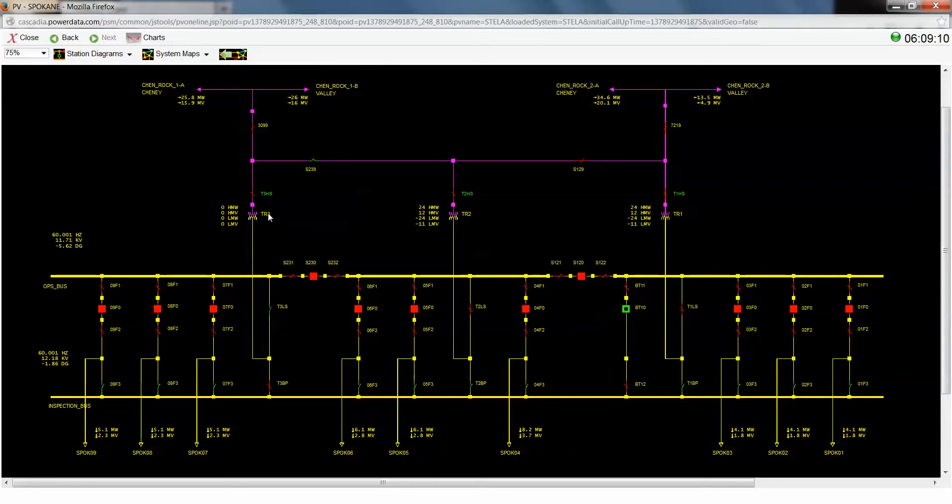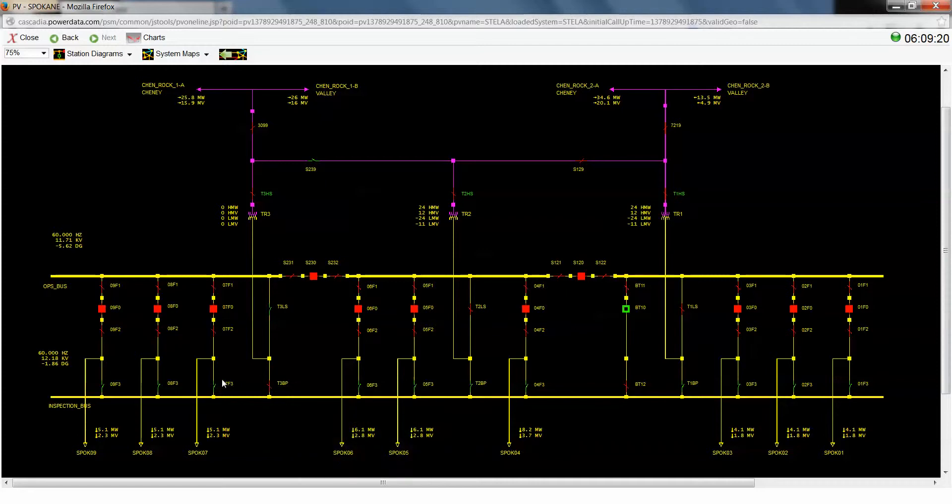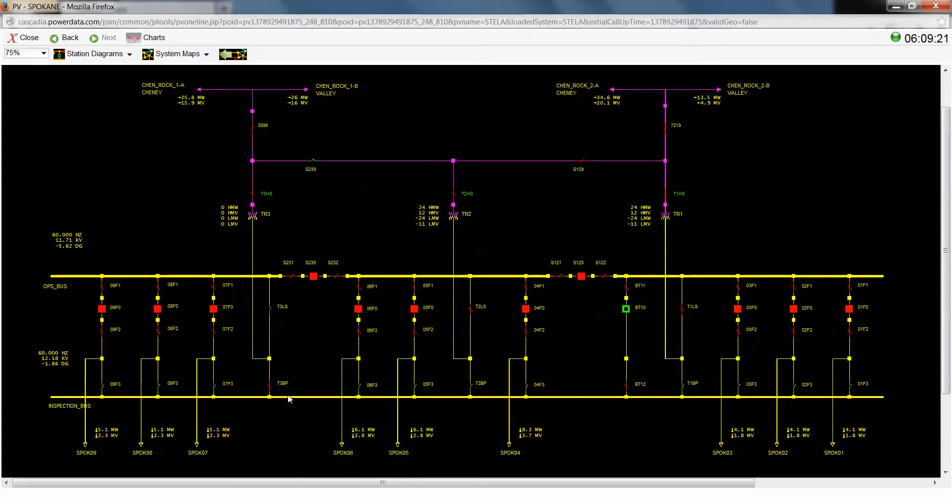So in order to properly isolate this transformer, we need to reopen this bypass switch, which is going to de-energize the low side, and it's also going to de-energize this inspection bus.